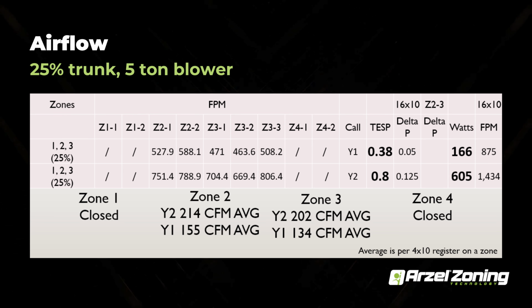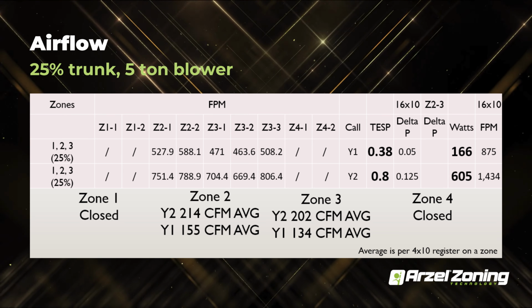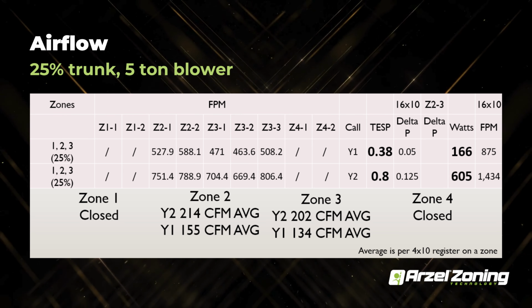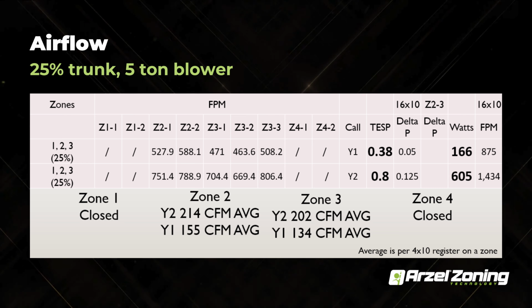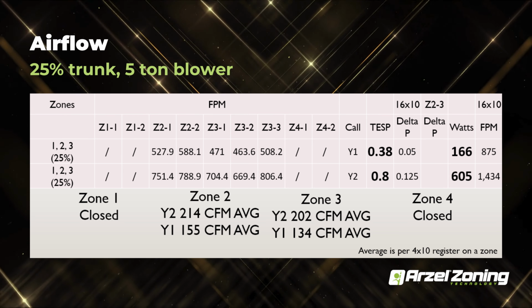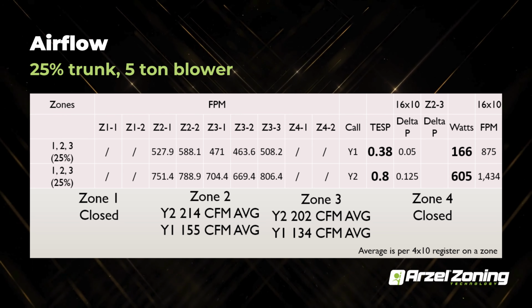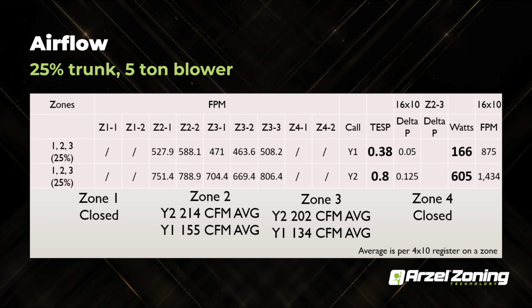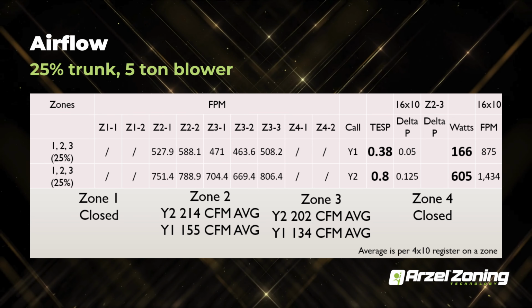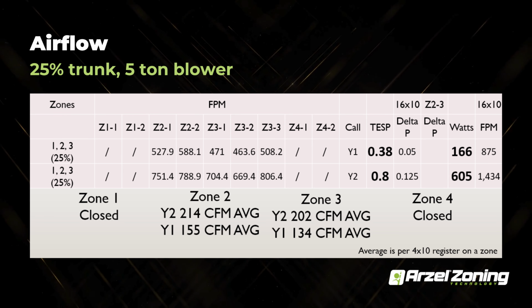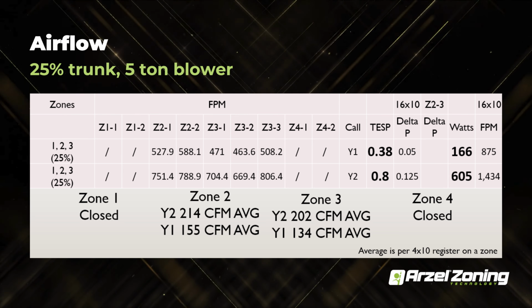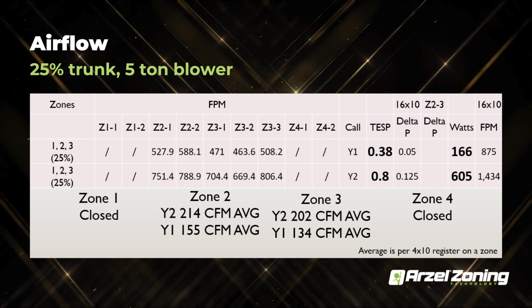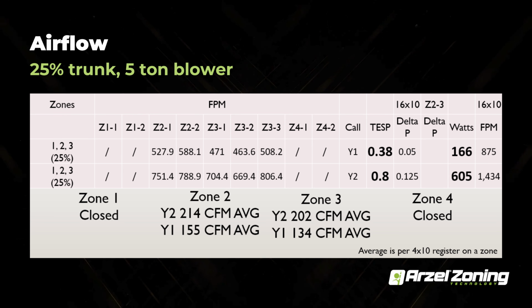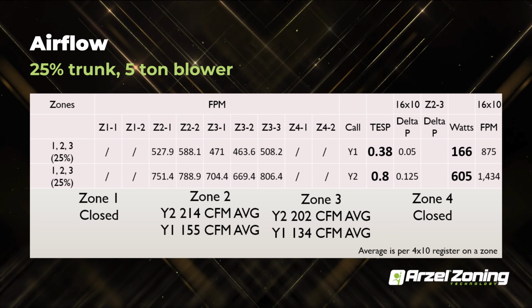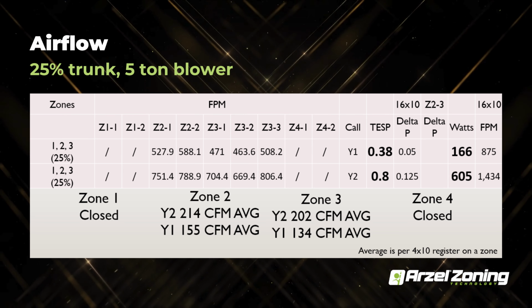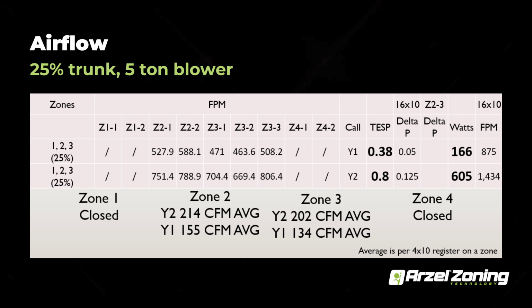So with this example here, when we were locked into first stage, we're at a 0.38 total external static pressure with 166 watts and 875 feet per minute on the registers themselves. Then on our Y2 output, you can see our total external system pressure is actually exceeding the maximum now. So we're at 0.8, typically about a 0.7 is what we strive for with zoning. Still, pay attention to your manufacturer's nameplate.